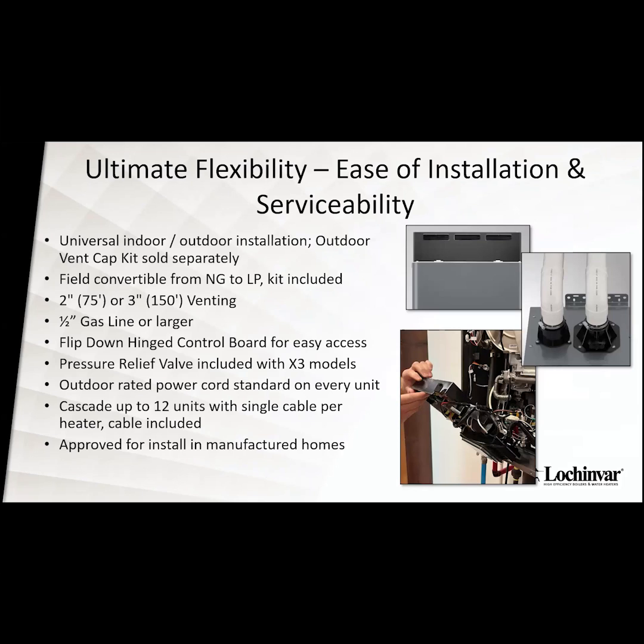So with the ease of install and serviceability on this unit, you can convert this unit into an outdoor unit, but I wouldn't recommend that for Montana at all. This does have a field convertible kit to go from natural gas to LP, which is included in every single unit, which we'll cover here in just a little bit. With 2-inch PVC, you can go 75 feet. With 3-inch PVC, you can go 150 feet. The gas connection on this unit is a 1/2 inch on the bottom of that unit.